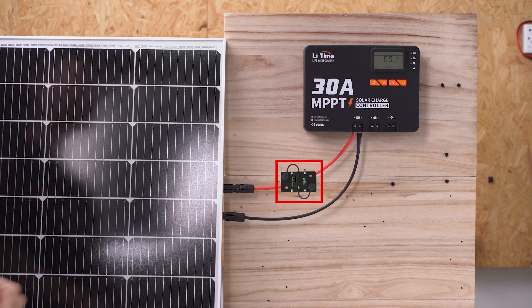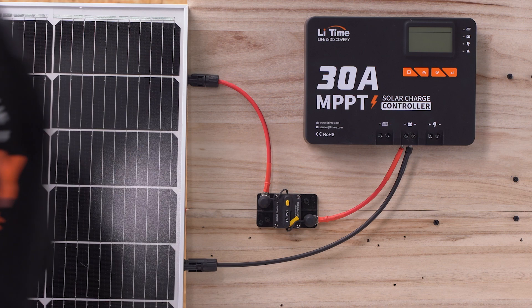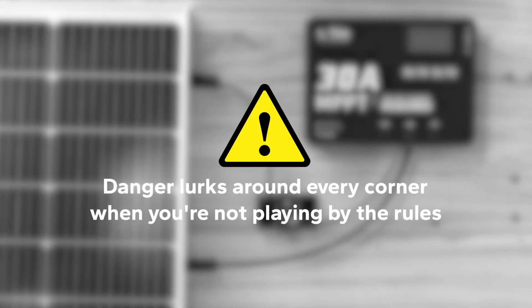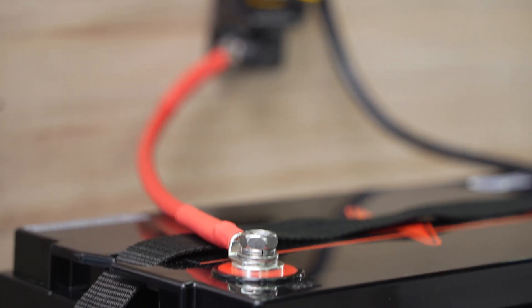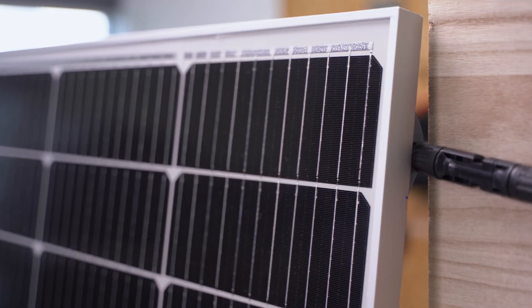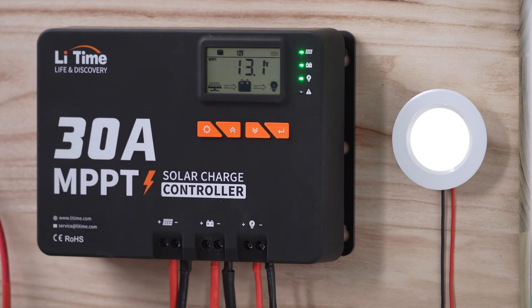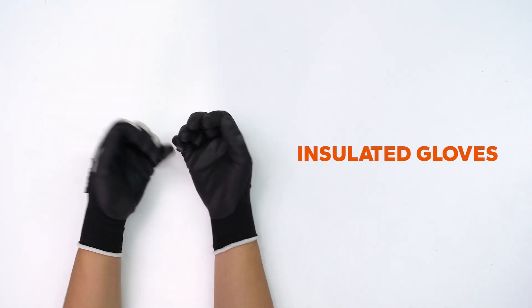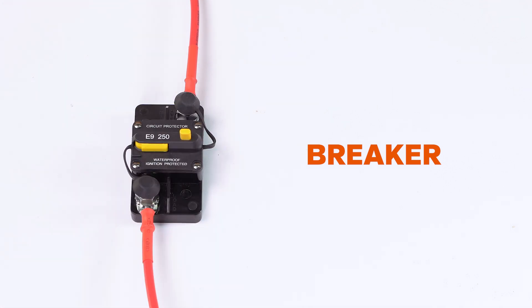Warning: Do not connect the solar panel without a breaker or fuse, and do not put the PV wire directly to the battery port. Danger lurks around every corner when you're not playing by the rules. In this video, we'll walk you through the steps to connect a LiTime 30A MPPT controller to your battery, solar panels, and DC load, and configure it to function well. For your safety, please make sure insulated gloves are worn throughout the operation and use breakers to avoid electric shock.